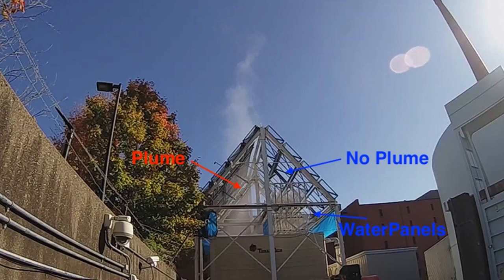Contamination of water is typically measured by testing its electrical conductivity, which increases with the amount of salts and other contaminants it contains. Water used in power plant cooling systems typically measures 3000 microsiemens per centimeter, while the water supply in the city of Cambridge is typically around 500 or 600 microsiemens per centimeter. The water captured by this system typically measures below 50 microsiemens per centimeter.